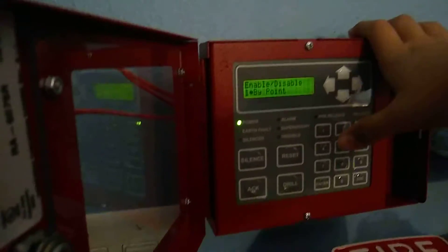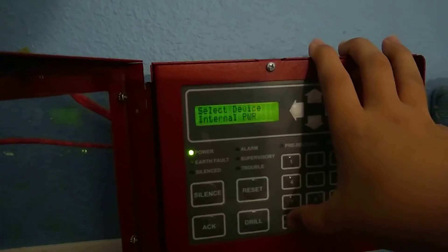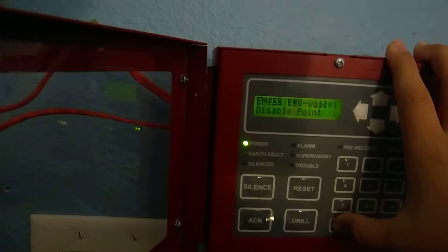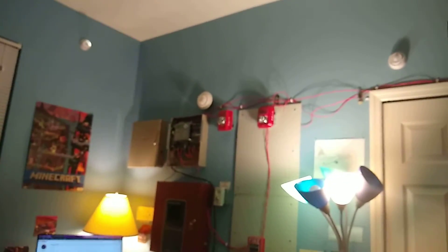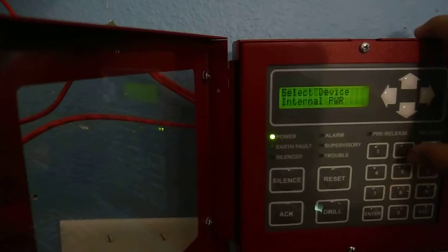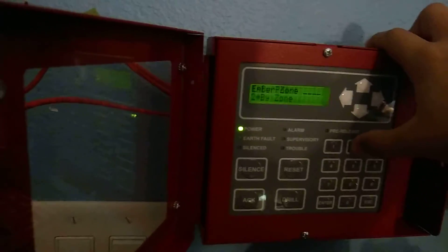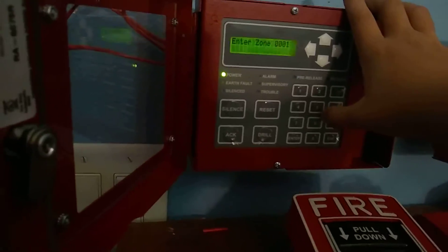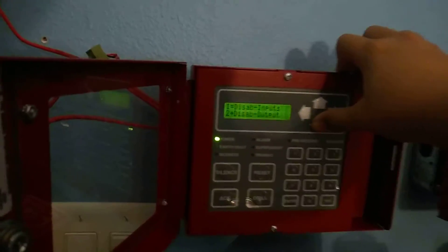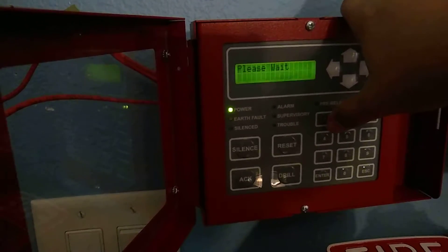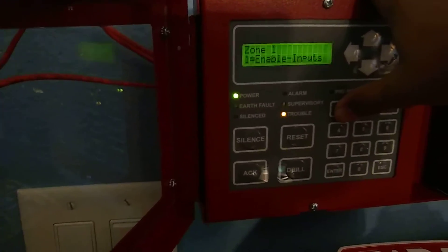You can disable by point or by zone. Let's try a point — it's running system sensor sync. If I do that it'll disable it, so now the panel is in trouble because it's disabled. If I press Enter again it'll enable it — now it's normal. By zone you can disable inputs or outputs; you can also re-enable by pressing one.